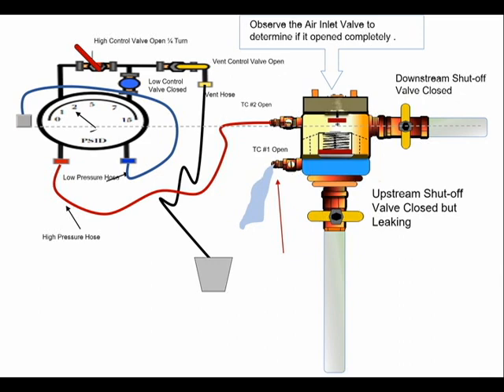Test cock number one should be sufficiently open to compensate for the inlet flow of water but not open significantly to cause the test kit needle or air inlet valve to drop due to the reduction in the inlet flow of water.